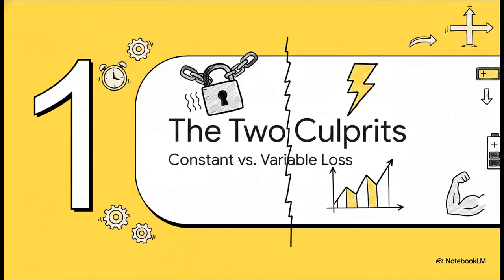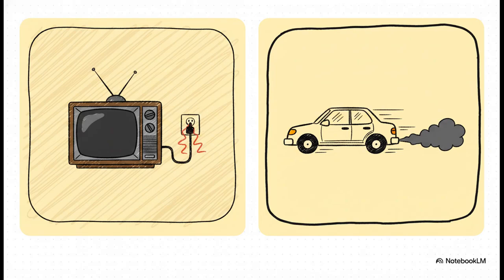So, our investigation starts by splitting the problem in two. It turns out that pretty much all transformer losses can be sorted into two main buckets. The ones that are always there no matter what, and the ones that change based on how hard the transformer is actually working. Think of it like this. On one side, you have core loss. This is kind of like the standby power on your TV. It's happening as long as a transformer is energized, even if it's not actually powering anything. But on the other side, you've got winding loss. This is more like the gas your car uses. The faster you go and the heavier the load, the more fuel you're going to burn.